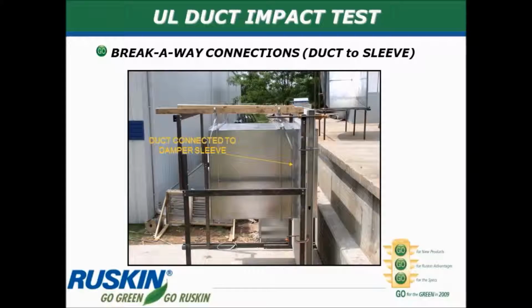So when we install a fire or a combination fire smoke damper in a wall, it is securely attached to that wall and it needs to stay in place. Even if there's a disaster with the building, say on one side of the wall the roof collapses, that damper must stay in place. If the roof collapsed onto the ductwork and yanked that damper out of the wall, now that wall would not be protected. There would be a big opening there where flame and smoke could pass through to the other side, and that violates our whole concept of compartmentalization. So the damper must stay in place. It must stay connected to the partition it is protecting.